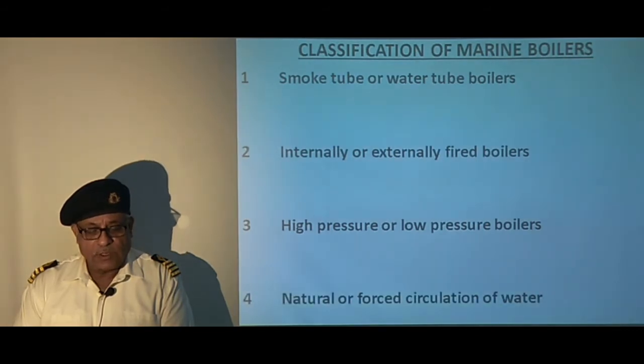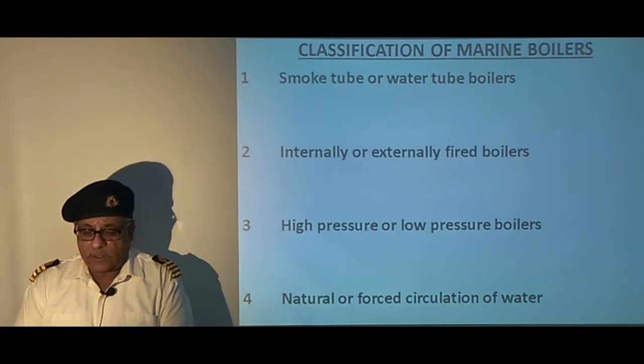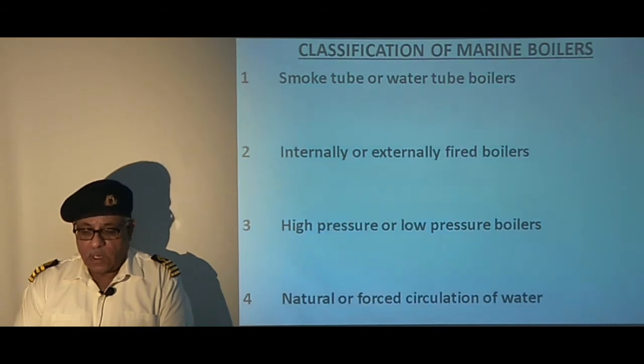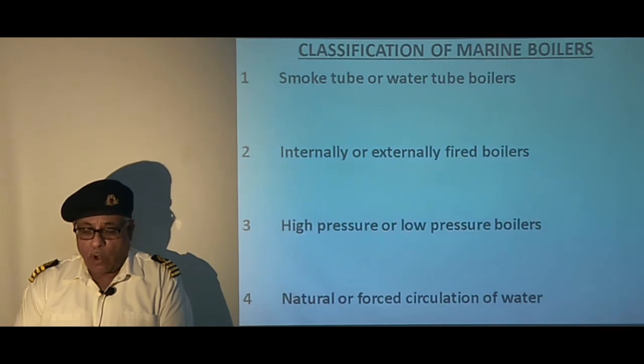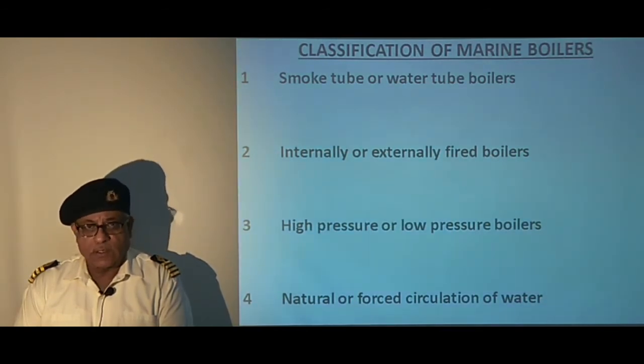The next classification is natural or forced circulation of water. Usually all internally or oil fired boilers have natural circulation of water. Those exhaust gas boilers on motor vessels which do not have their own reservoir of water and steam are called forced circulation boilers, as water from the internally fired boilers is circulated through the heating coil using a pump. Similarly, supercritical steam generators also fall in the category of forced circulation boilers.